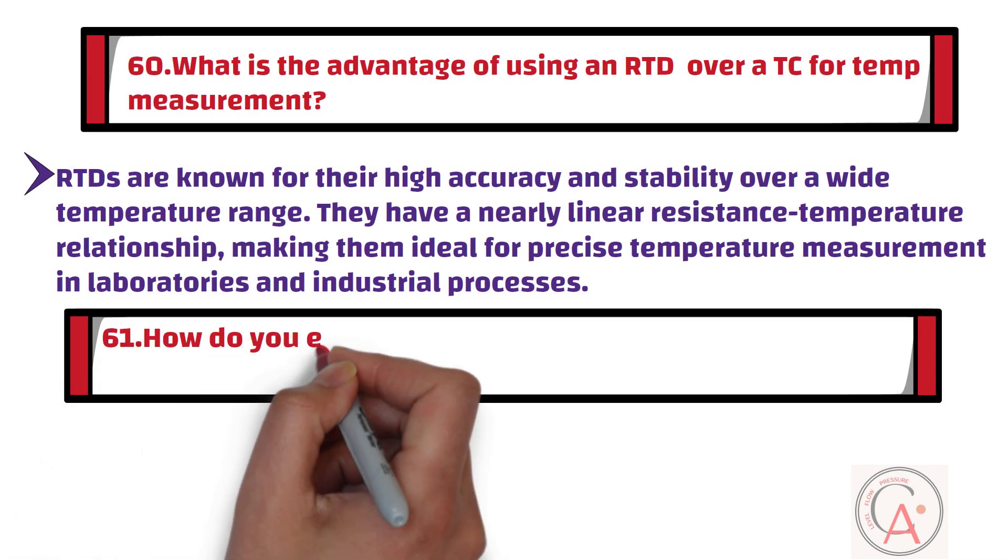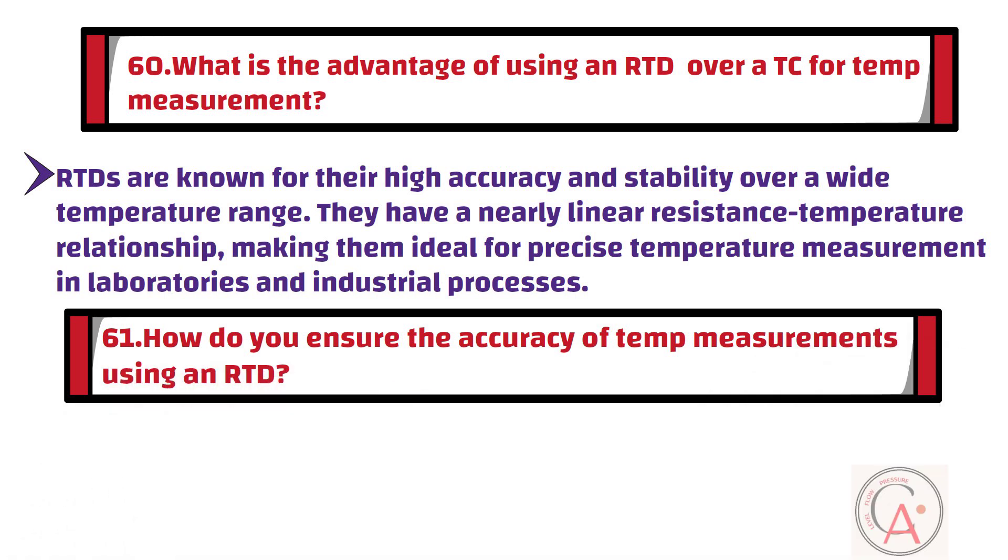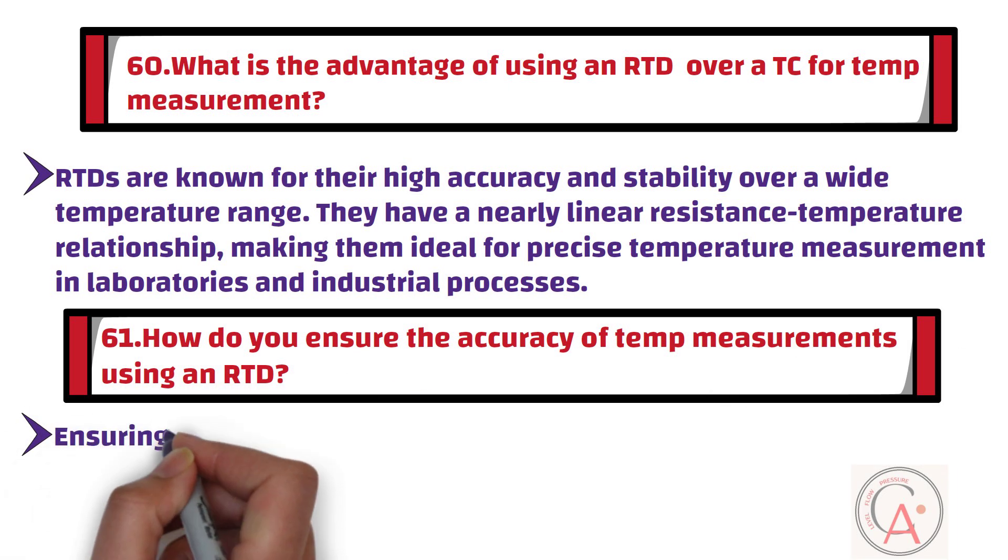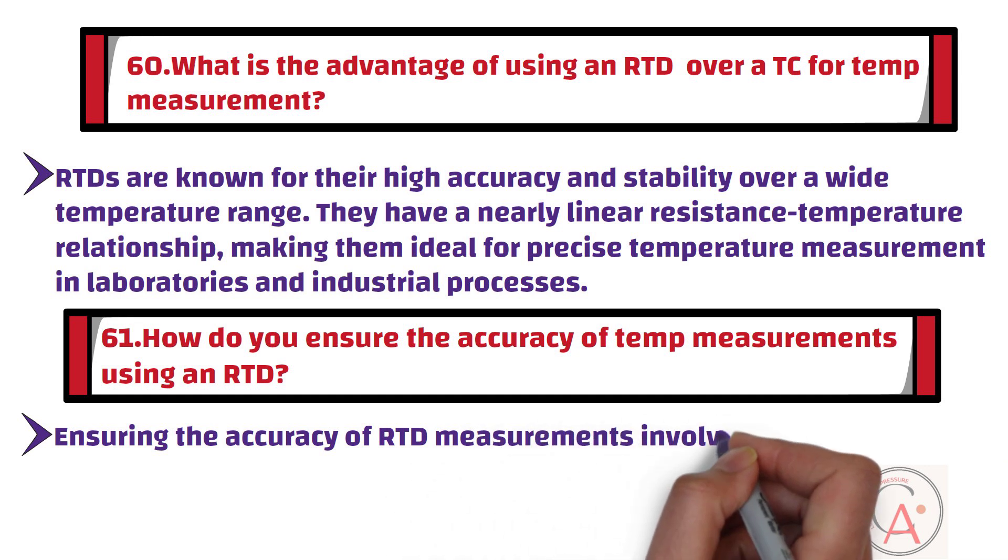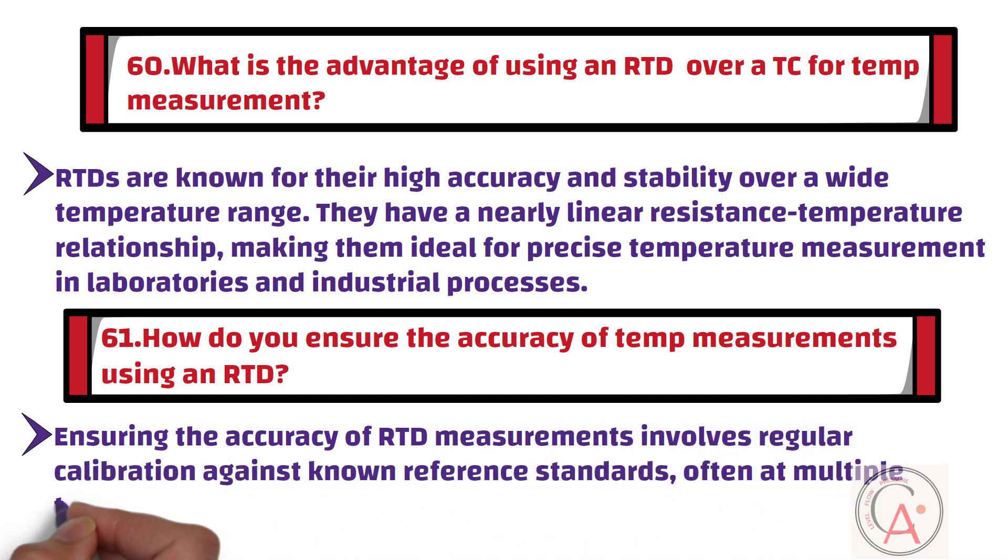Question number 61: How do you ensure the accuracy of temperature measurements using an RTD? Ensuring accuracy of RTD measurements involves regular calibration against known reference standards, often at multiple temperature points. The use of precision resistors in the measurement circuit and proper lead wire compensation are also essential.